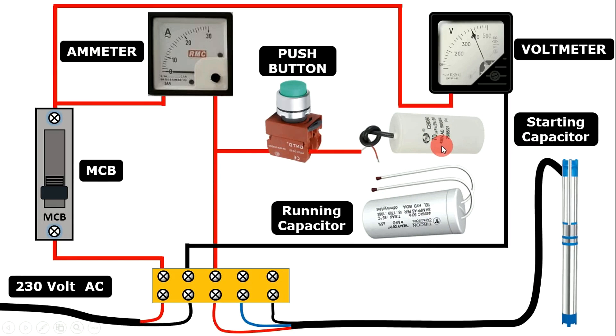From the second terminal of the starting capacitor, take a wire and connect it with one wire of the running capacitor — that is, connect starting capacitor and running capacitor in parallel. Now from this connection, connect a wire and connect it with the starting wire of the pump, that is with the fourth terminal of TB.